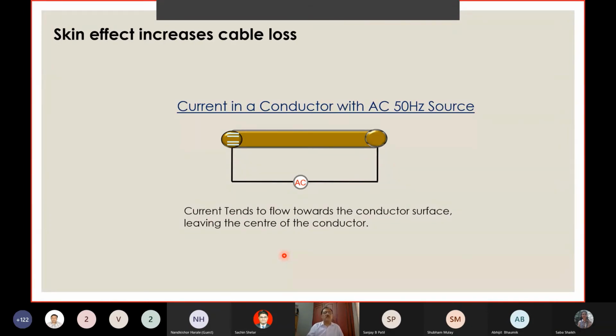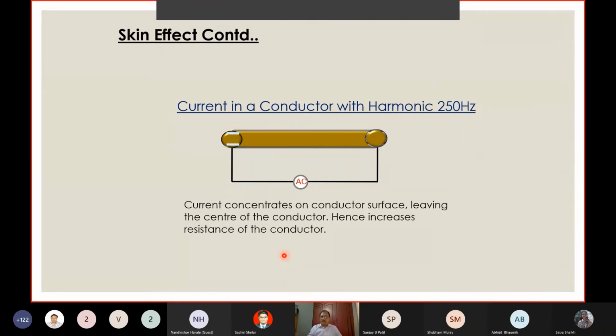Now, there are two distinctive ill effects of the harmonic, and I thought it is important for you to visually see it and appreciate it. See, when you use a DC current on a conductor, you will find that the current will flow through the entire conductor cross section. Whereas when you go to an AC current, the current will flow closer to the periphery. So the core will be cooler. You must have seen this in most of the cables. When you touch the cable, you will feel the heat, but the core of the cable will not have this heat. If you have a 250 Hertz harmonic current, fifth order harmonic current very high, you notice that it flows only across the periphery of the cross section.